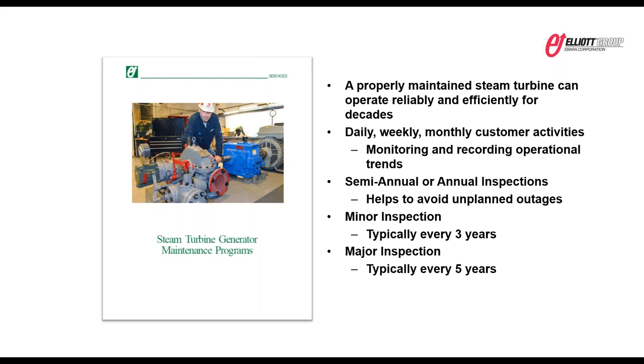You're going to look at safety devices, making sure the trip mechanism and all that is functioning properly. You might do an oil analysis from the oil system just to make sure the oil is clean, because two things, clean, dry steam with clean water chemistry, and clean oil, will really help your unit run reliably for years.